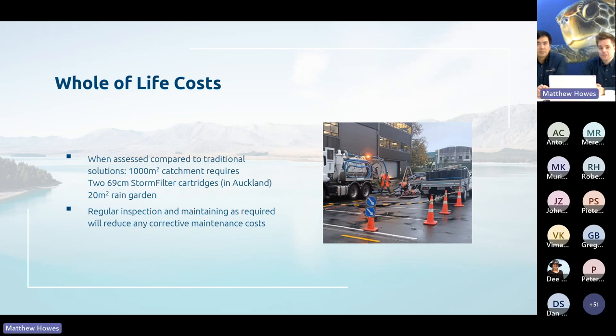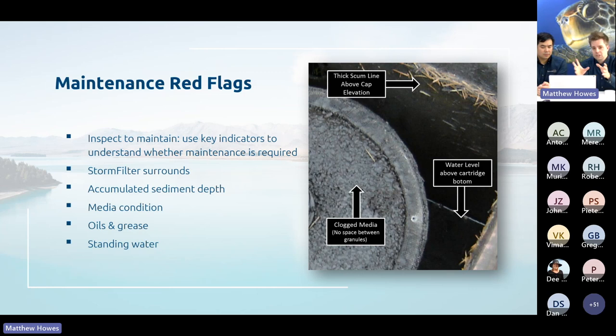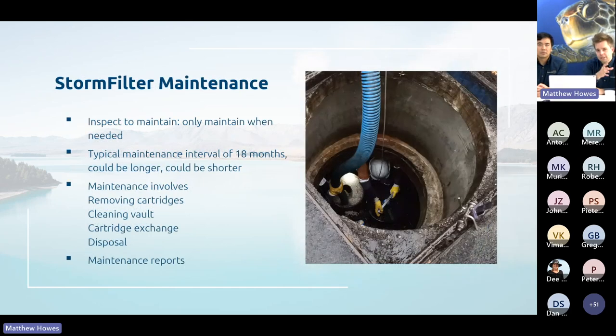Regular inspection and maintenance is important — the key point is that you don't maintain regularly, you inspect regularly and then maintain when needed. We look at the surrounds of the Storm Filter for good access, accumulated sediment depth, the condition of the media (which is why it's important that the hood is easy to lift), any oils and grease, and standing water. If any of those reach a certain level, that triggers a maintenance. You only maintain once inspection has verified you need it.